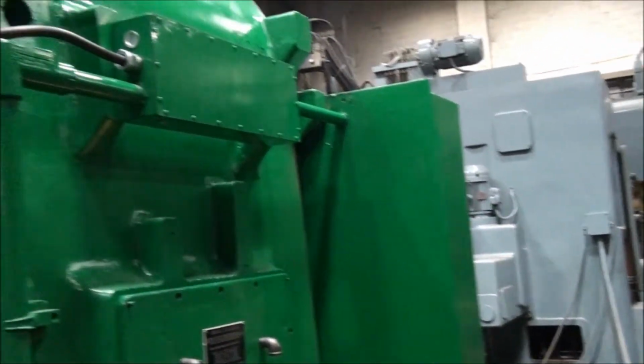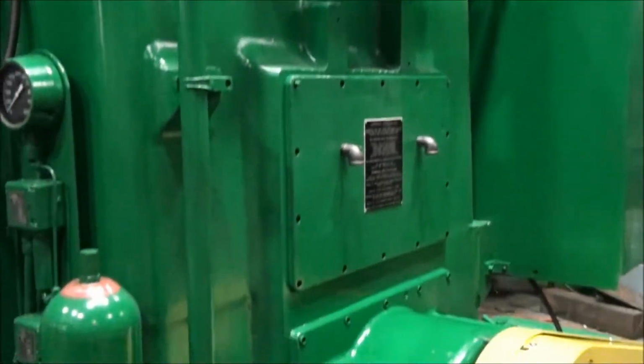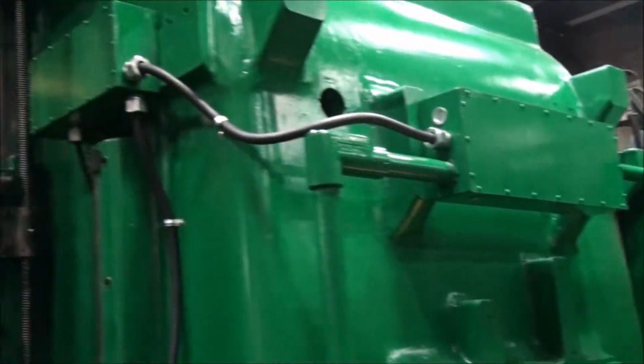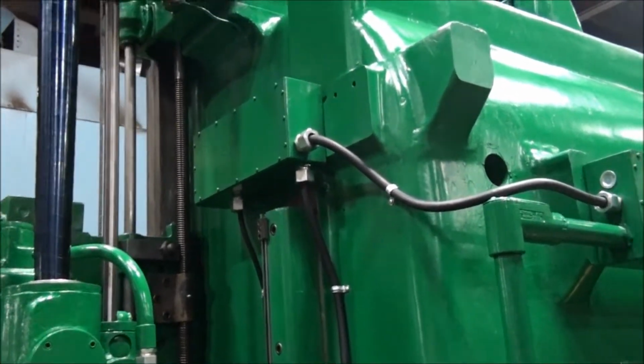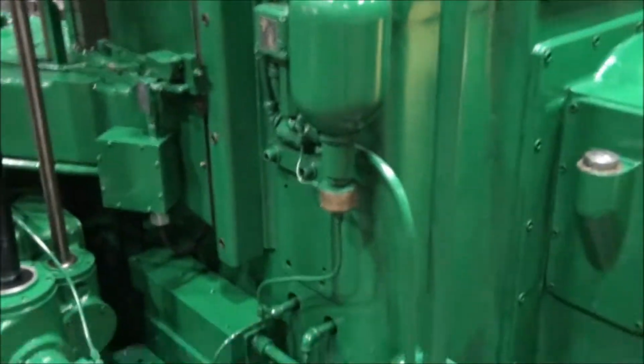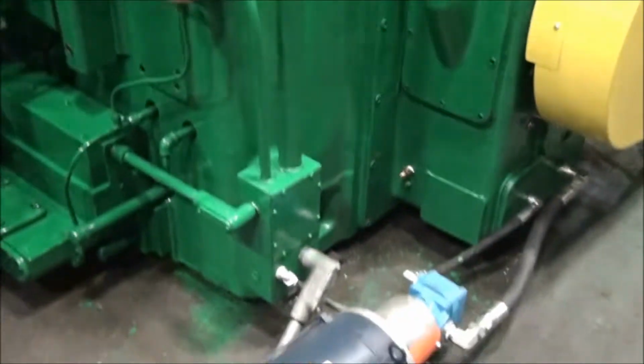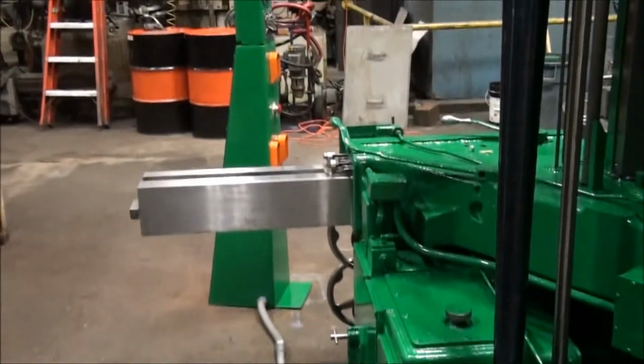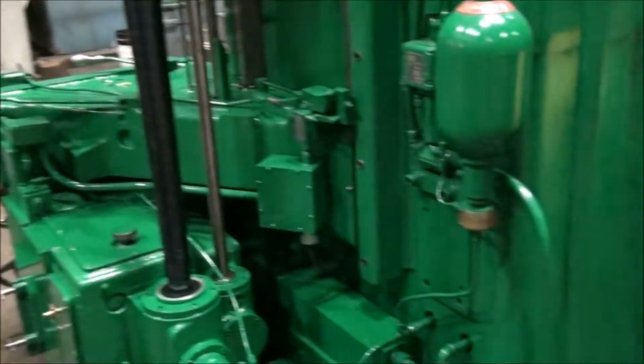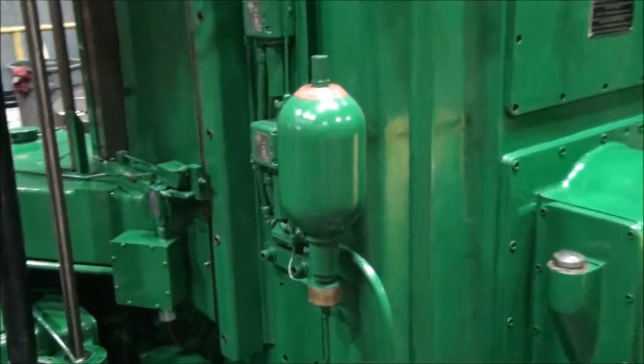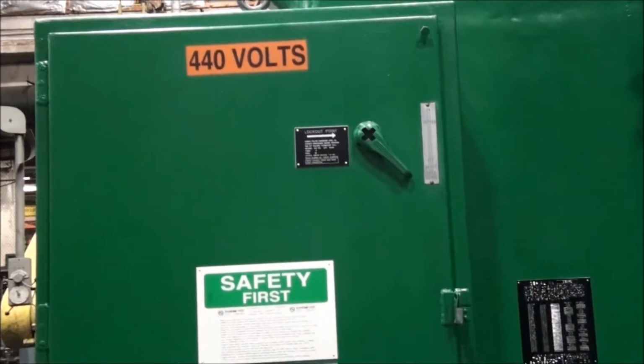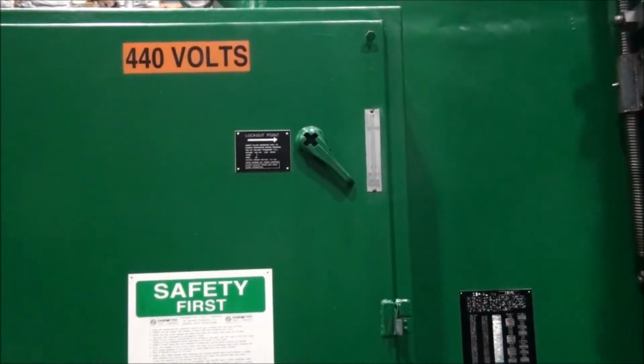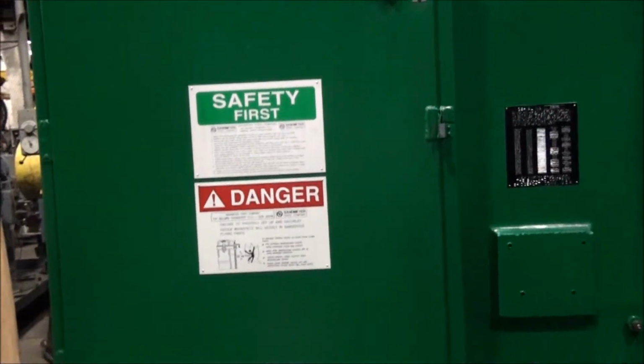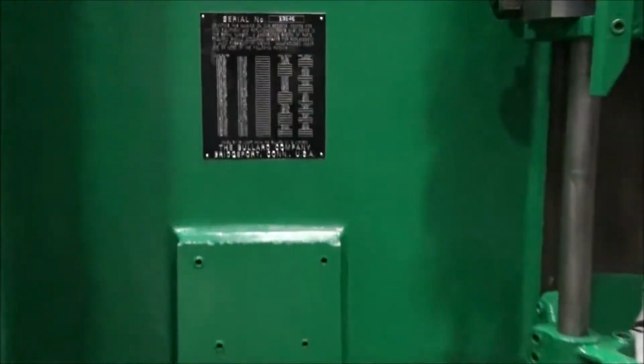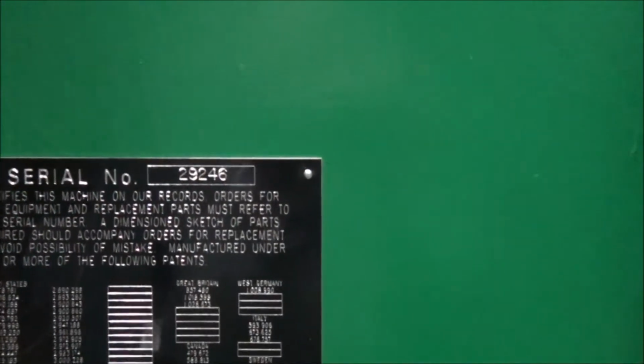We set up the electrical to include spares running from the main electrical cabinet to a rear junction box, as well as the side column junction box. In addition, the pendant and side head junction boxes also are equipped with multiple spares, which should allow installation of the fixture assembly. The machine has been set up for operation on 440 volts. The lockout point has been identified for the machine. The serial number is 29246.